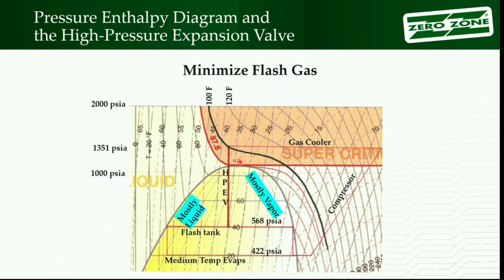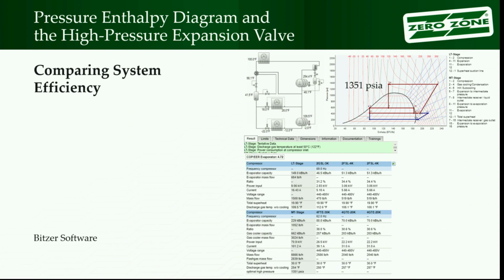So as we look at these simulations from the Bitzer software, we're going to look at where that line is dropping in and how that line shifts to the right or to the left as we change the pressure in the system. So I went in and selected some compressors, locked them in so the compressors didn't change, let the software go back and calculate the system pressure that it should run at, and it came back and said 1351. Odds are if you went into a controller and it was running, it'd come back and say it'd run 1351.